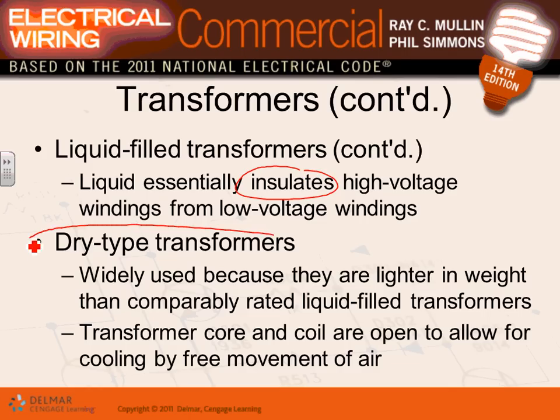A lot of people, guys, specify dry type transformers for smaller buildings. They are cheaper and lighter. Dry type means there is no liquid inside them, so you don't have to have liquid containment and what's not. And if you have liquid, and if it's flammable liquid, you have to put them in a vault or outside. You can't put them inside the building.